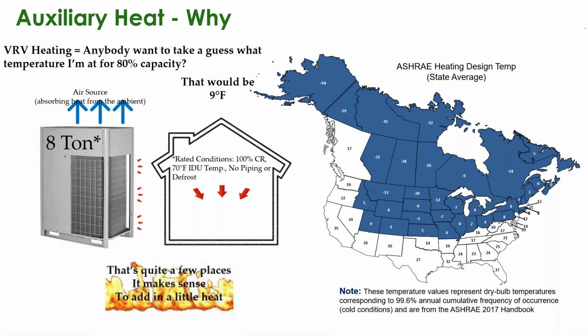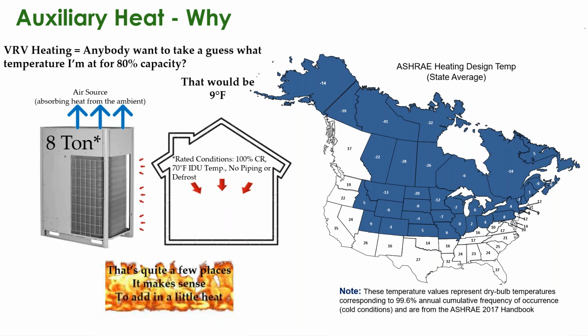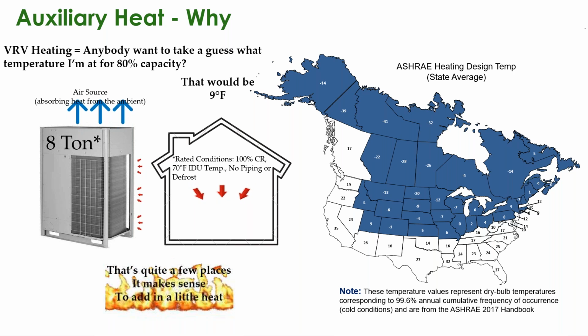As I said, oversizing is possible with variable refrigerant systems, but you still have to consider the overall impact and the pros and cons of it. If you end up grossly oversized, especially on the cooling side, you can cause harm to that system, make it have a harder life because it's running at low operating conditions for an extended period of time, which will result in short cycling, owner discomfort, possibility of oil control issues.